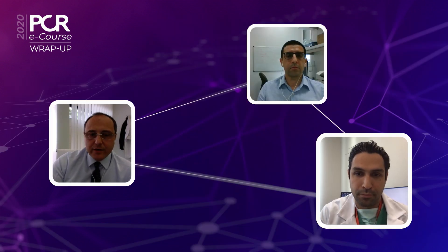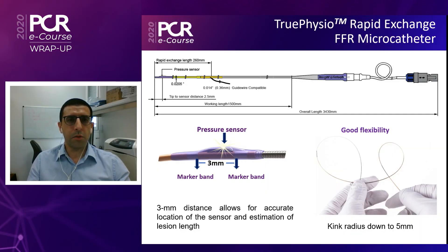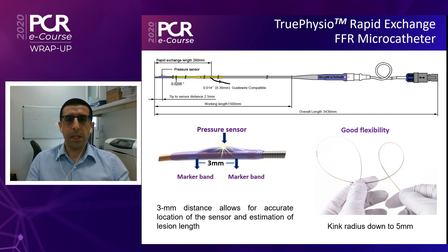We also have a new device — the True Physio FFR microcatheter. The pressure sensor is located between two radiopaque markers, which are easy to locate on angiography during pressure measurement. It has a small profile to minimize problems in tortuous vessels, and a short distal blind section with a distance from the tip to the sensor of 2.5 millimeters. The microcatheter also has good flexibility and pushability, which are important features when dealing with tortuous vessels or when making post-PCI measurements, where you need to pass through a recently implanted stent.